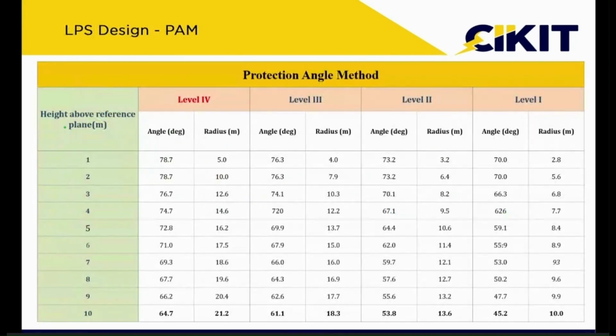So we have already performed the calculations and we have found out this angle for different heights. So here you can observe that for 10-meter height, as shown in the example, the angle will be 45 degrees for level 1. In level 2, it will be 53 degrees, for level 3, it will be 61, and for level 4, it will be 64 to 65 degrees. For corresponding angles, we have found out the radius. So if you take 10-meter height above the plane, the radius will be around 21 meters. So this is how we have to calculate the radius of protection for the protection angle method.